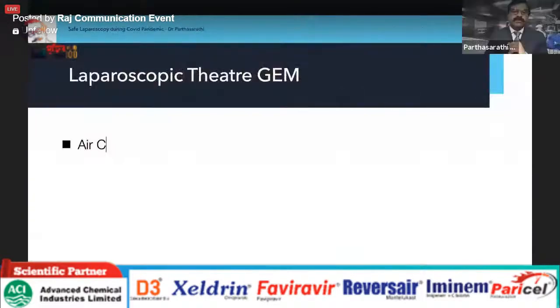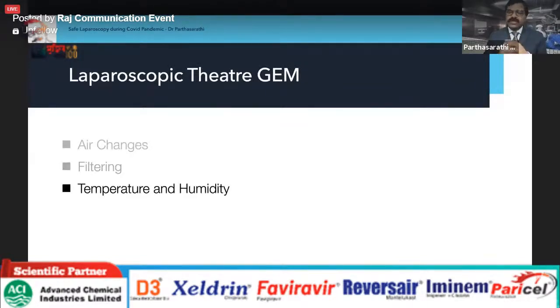And particularly coming to the OT, we have to consider a lot of changes, particularly the air changes: how many cycles of air rotation in the OT, the filtering system and whether anything needs to be improved there, and then temperature and humidity. Normally we follow the NABH norms here. This is an NABH hospital, and we want to go one step higher for this COVID time.